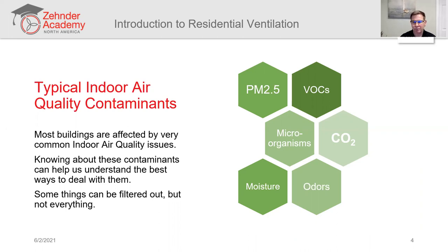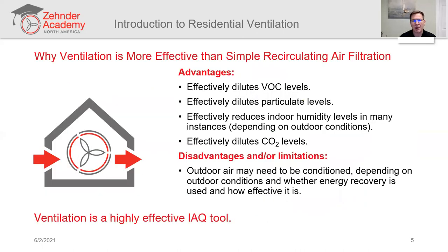And one solution, such as filtration, common thought that people have is, if you got air quality problems, then throw a filter in. But filters can't deal with everything. And so that's where we turn to ventilation. Ventilation is actually pretty effective at dealing with just about all of these air quality issues. So it effectively dilutes VOC levels. It effectively dilutes particulate levels. It effectively reduces indoor humidity levels depending on the climate and where you're at, but in many climates, it's a good way for controlling humidity.